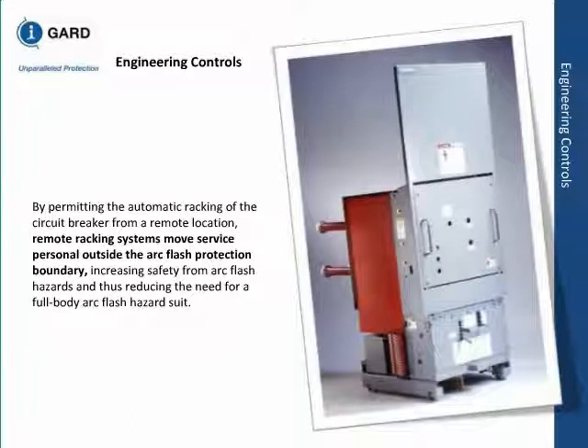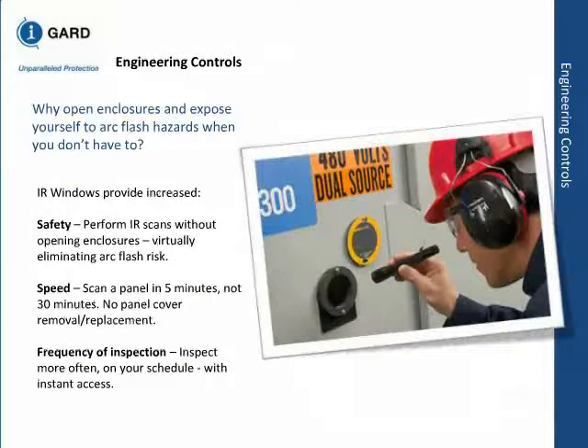One technology people are not using, which is very excellent, is infrared windows. Infrared tells you the temperature is rising and arcing is liable to happen, or arcing is already happening. You can open the door and check it, or put infrared windows in during the design stage, so you can check that hot spot or something from outside. If you're familiar with NFPA 70E 2012 Table 130.7 C15, it'll give you what protective clothing you need when you are doing infrared thermography.